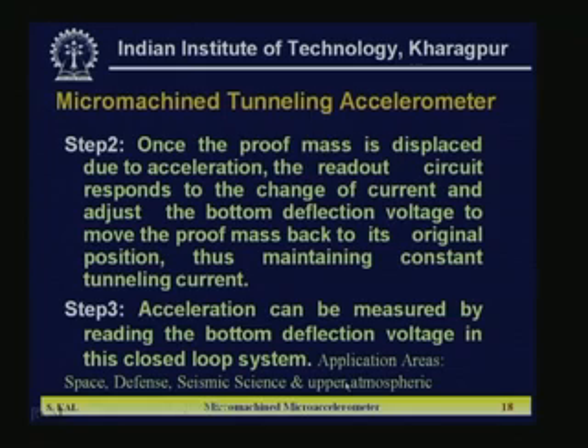After that, step 2: once the proof mass is displaced due to acceleration, the readout circuit responds to the change of current and adjusts the bottom deflection voltage to move the proof mass back to its original position, thus maintaining constant tunneling current. So you see this approach. Change of current is very difficult to measure. So what are they doing? Because of the acceleration, the tip is going down and the current is going to change.